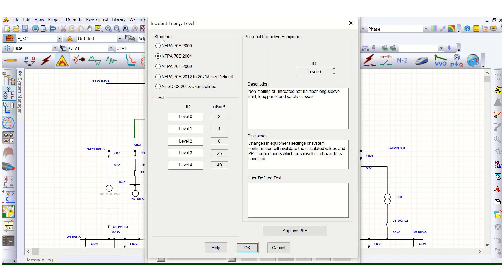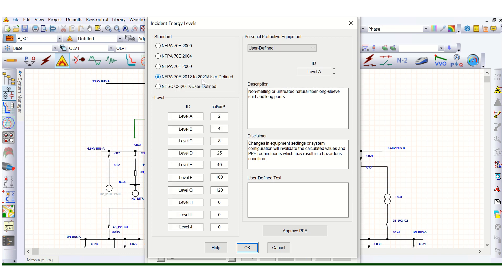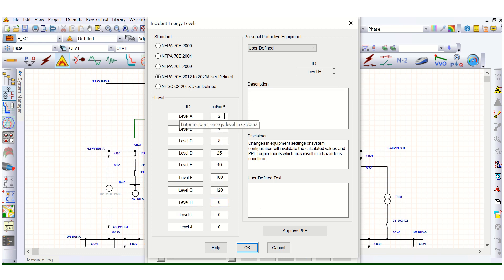One important thing to notice: if you go to 'Edit or Approve PPE,' here are the standards. As per NFPA 70E 2004 there are levels 0, 1, 2, 3, 4. We will go as per NFPA 70E 2012 to 2021, where you can see there are many levels — A, B, C, D, E, F, G — and the energy levels defined are 2, 4, 8, 25, 40, 100, and 120 calories per centimeter squared.